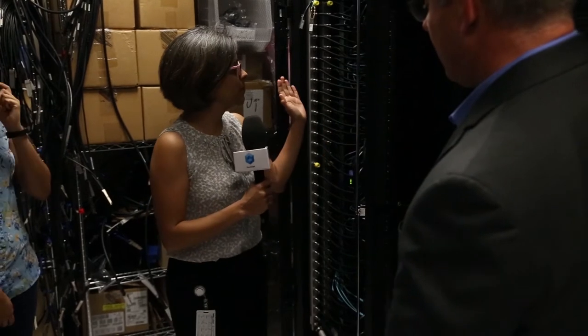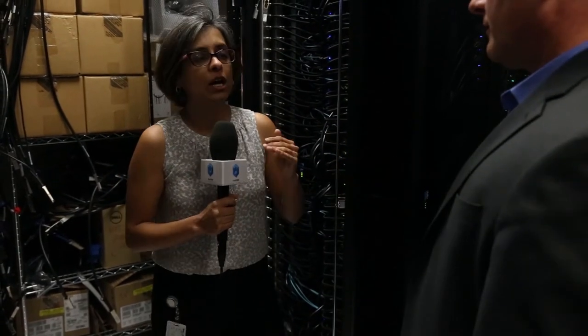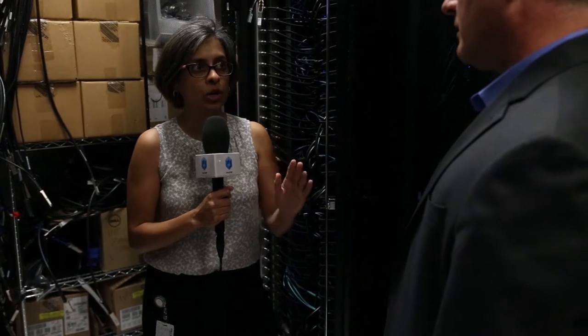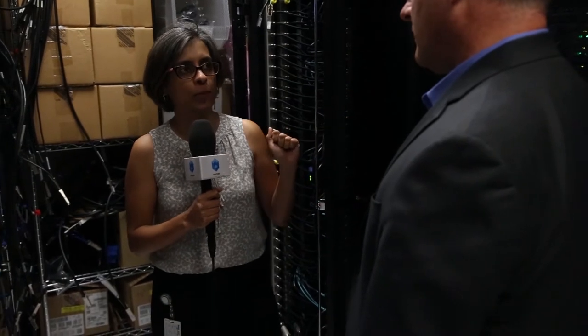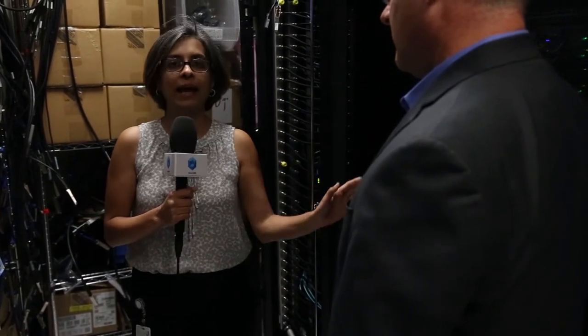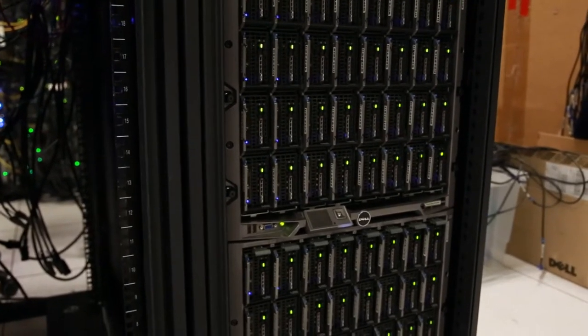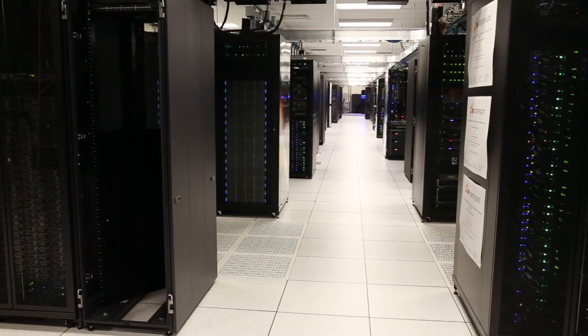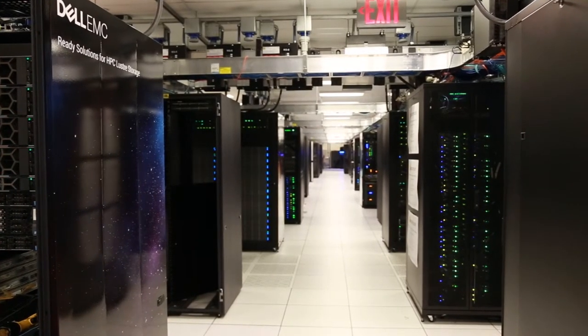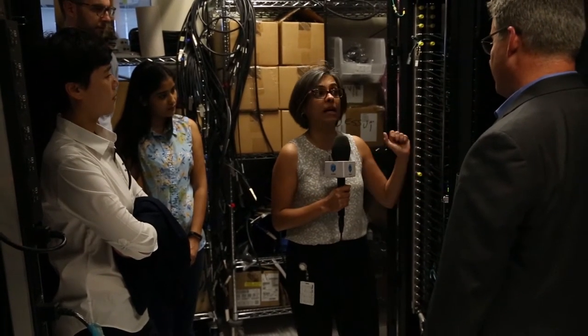In our early studies, we've seen that your efficiency — how much performance you get out of the server — should not differ between air-cooled and liquid-cooled, if your air-cooling solution can provide enough cooling for your components. So if you have a well air-cooled solution, it's not going to perform any worse than a liquid-cooled solution. What liquid cooling allows you to do is, in the same rack space, put in a higher-level configuration — higher TDP processors, more disks — a configuration that cannot be adequately air-cooled. That configuration, in the same data center space with the same airflow, you will be able to liquid-cool.